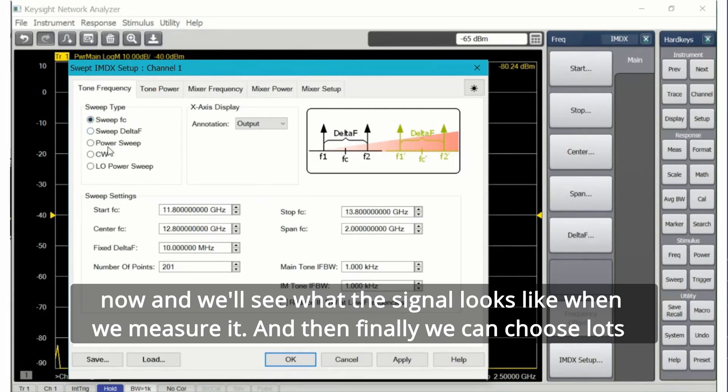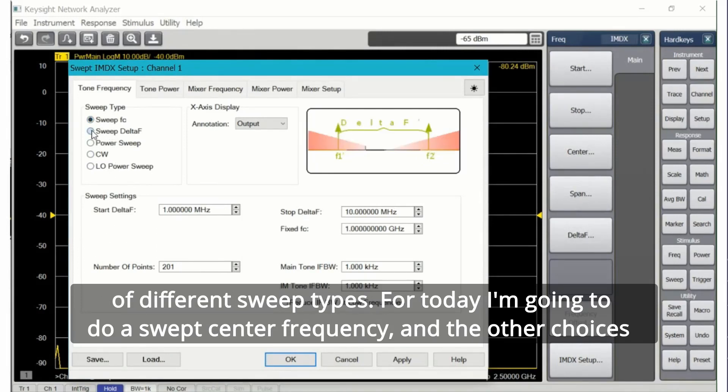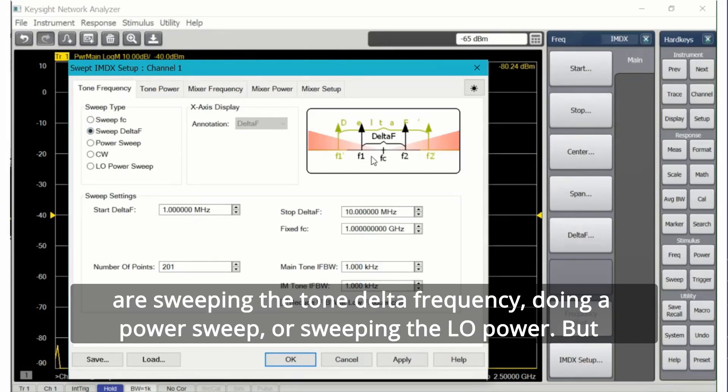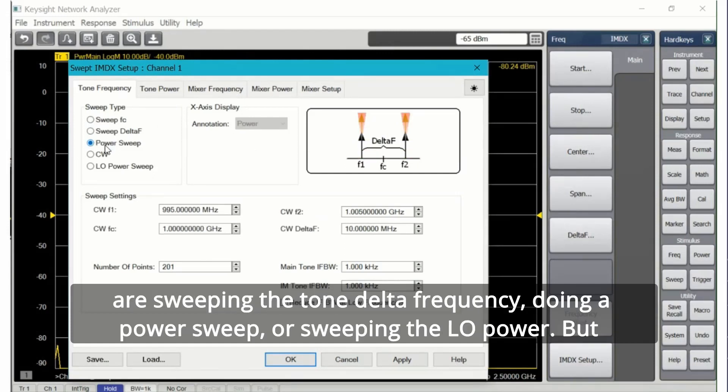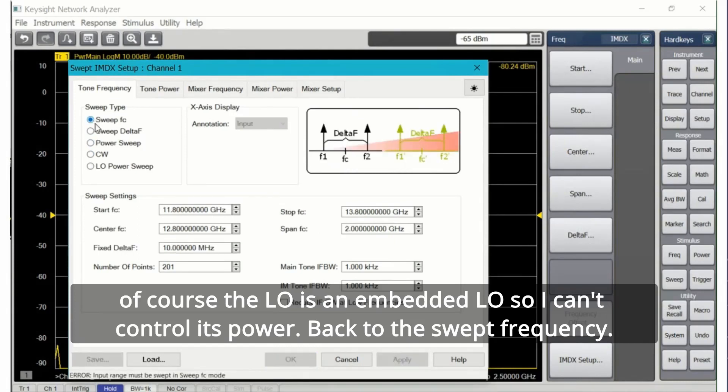Notice I've got the IF bandwidth for the receiver. We can set it differently for the main tone which is a high level signal compared to the IMD tone. Let's leave it at 1 kilohertz for now and we'll see what the signal looks like when we measure it. Then finally we can choose lots of different sweep types.